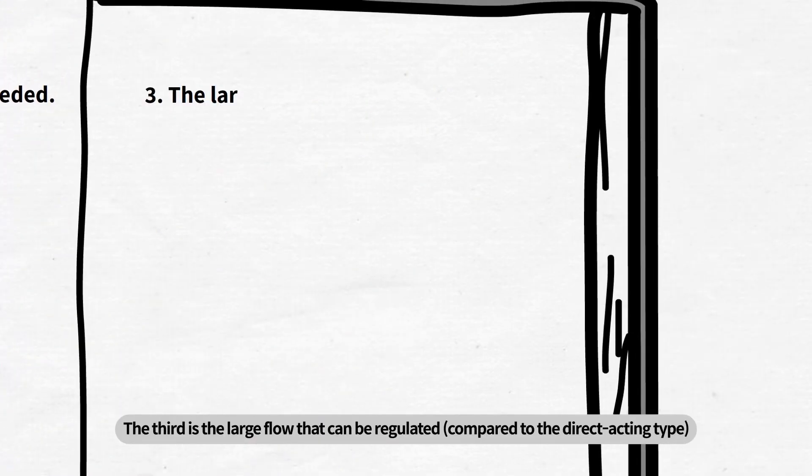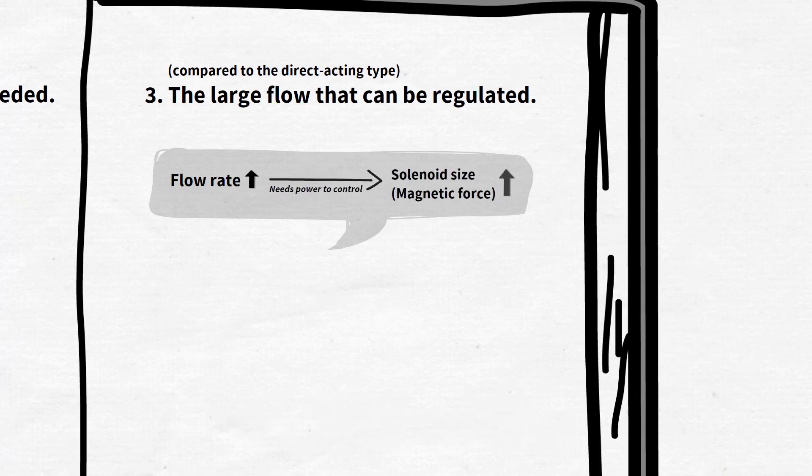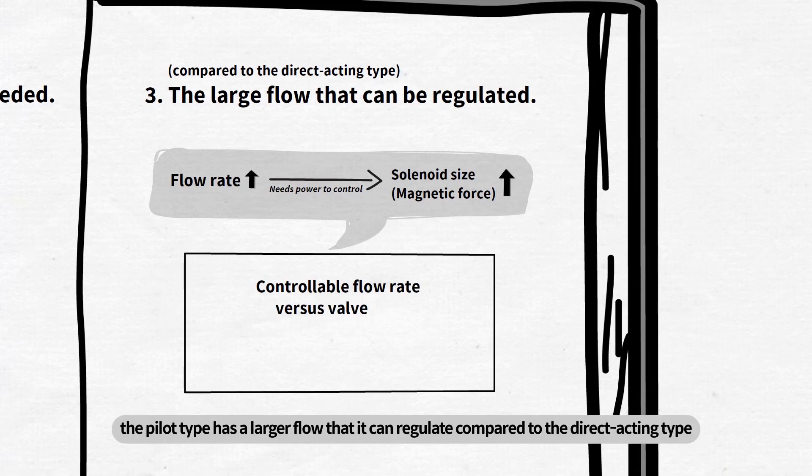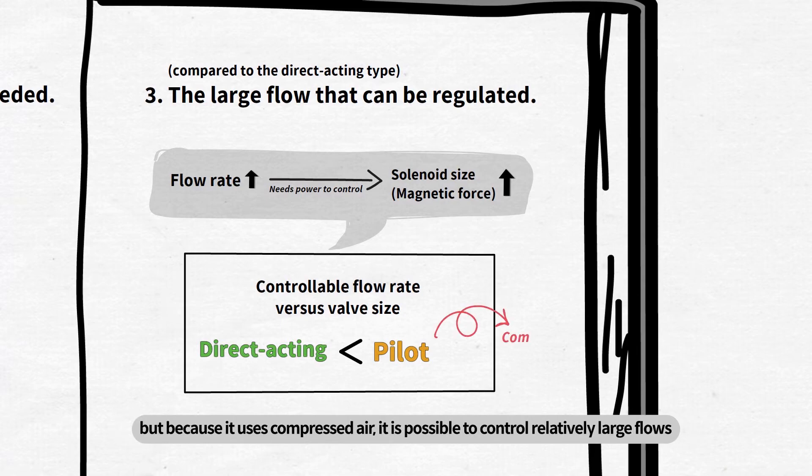The third is the large flow that can be regulated. The solenoid must be larger to control larger flows. When comparing with similar valve sizes, the pilot type has a larger flow, so it can regulate compared to the direct acting type. The pilot type does not control flow solely with the magnetic force of solenoid valve, but because it uses compressed air, it is possible to control relatively large flows.